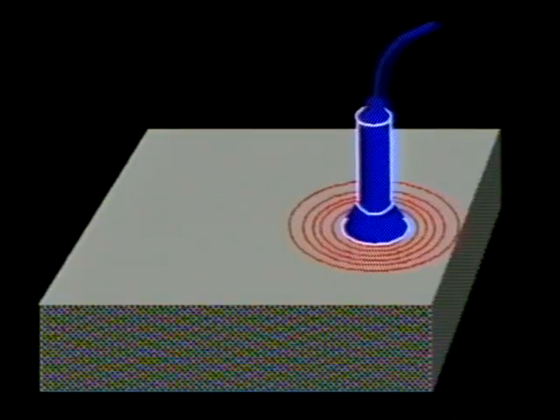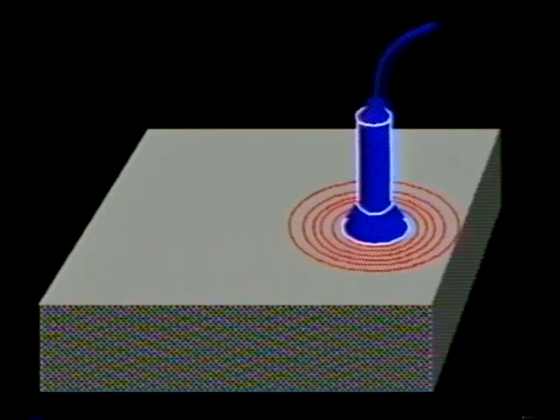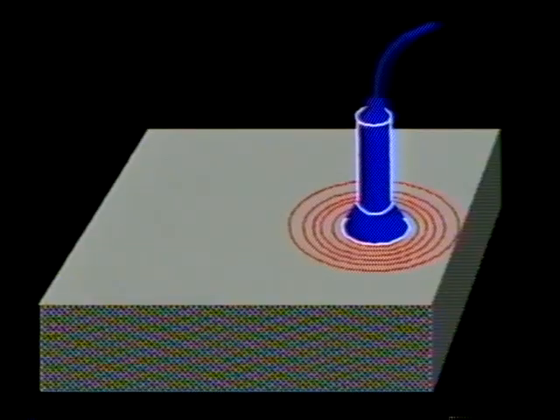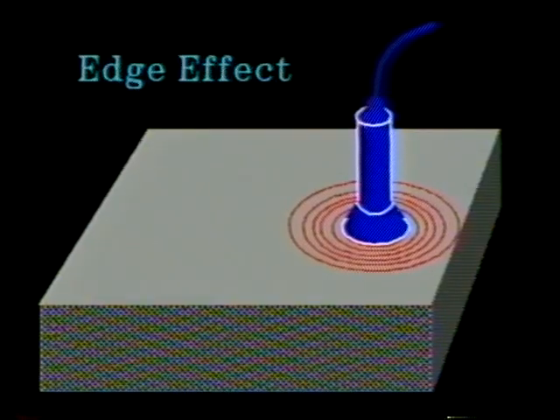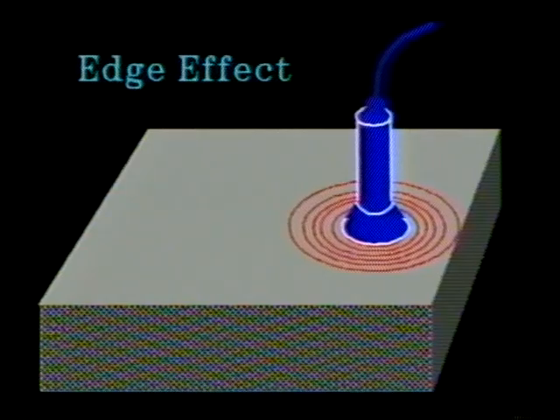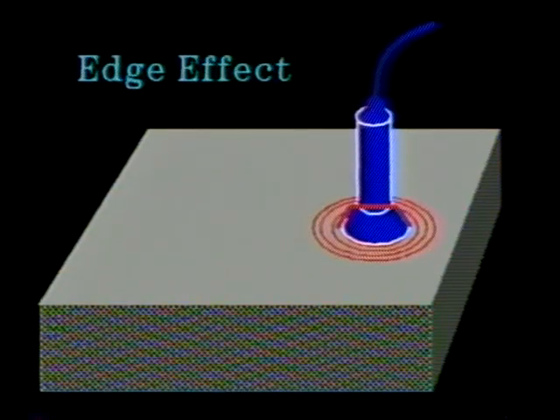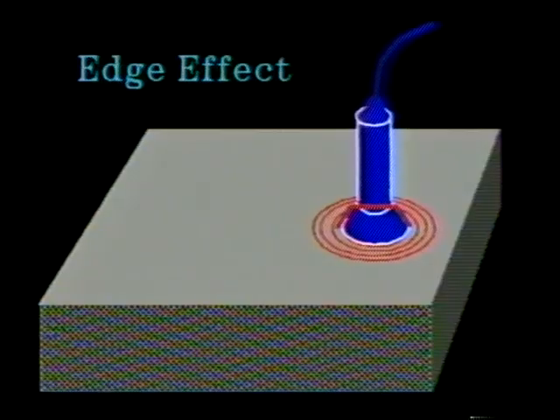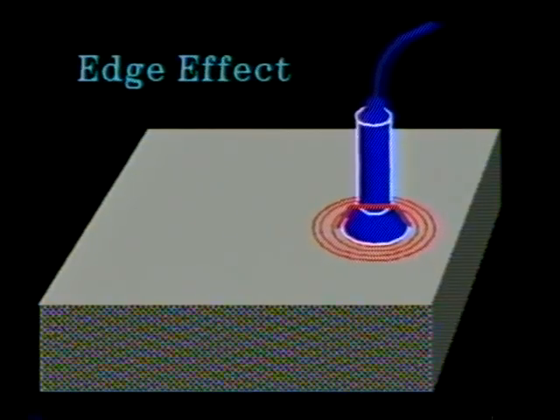As the coil approaches the edge of a test object, eddy currents become distorted by the edge signal. This is known as edge effect. Response to the edges of test objects can be reduced by the incorporation of magnetic shields around the test coil or by reducing the test coil diameter.